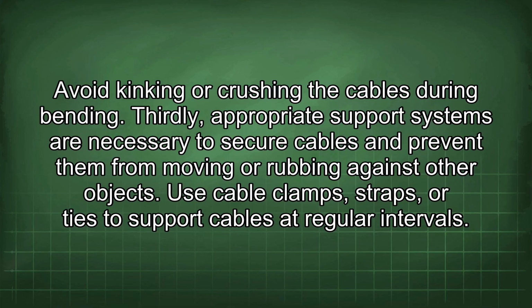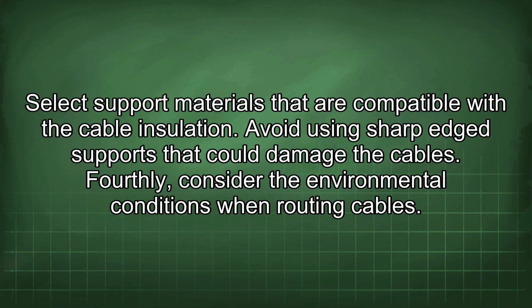Use cable clamps, straps, or ties to support cables at regular intervals. Select support materials that are compatible with the cable insulation. Avoid using sharp-edged supports that could damage the cables. Fourthly, consider the environmental conditions when routing cables.